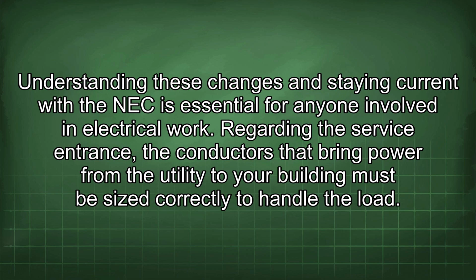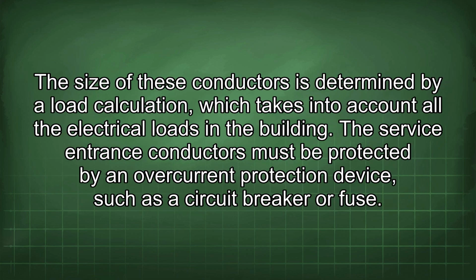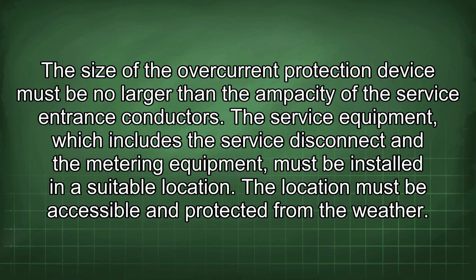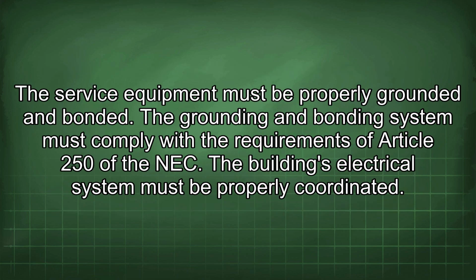Regarding the service entrance, the conductors that bring power from the utility to your building must be sized correctly to handle the load. The size of these conductors is determined by a load calculation, which takes into account all the electrical loads in the building. The service entrance conductors must be protected by an overcurrent protection device such as a circuit breaker or fuse. The size of the overcurrent protection device must be no larger than the ampacity of the service entrance conductors. The service equipment, which includes the service disconnect and the metering equipment, must be installed in a suitable location. The location must be accessible and protected from the weather. The service equipment must be properly grounded and bonded. The grounding and bonding system must comply with the requirements of Article 250 of the NEC.